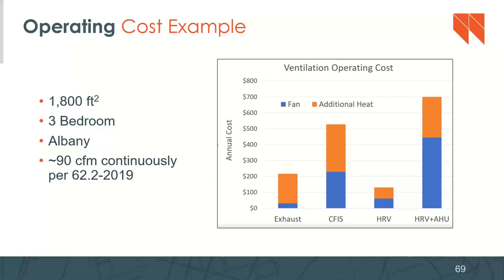What about the operating costs? Here is a very specific example for an 1,800 square foot three-bedroom home in Albany. Actually, it probably wasn't a home. I think it was a dwelling unit, an apartment. At 90 CFM continuously, which would be the amount required by 62.2-2019, this is what the operating costs were by the different types of ventilation systems you could do. The electrical energy required to run an exhaust-only fan was pretty low, but there's no heat recovery, and so the additional heat needed to condition that outside air brought it up to, let's say, $210 for an annual cost.